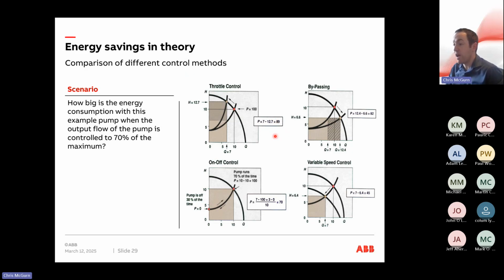So you'll see that by lowering the speed to 70% of the maximum, while using throttle control, you're down to 89% of the overall power. By bypassing, you're at 82%. On-off control, switching it on and off, 70% of the time, you're down to 70% load. But with variable speed control, you're bringing it right down to 45%. So there are significant savings to be had by removing these mechanical controls and replacing them with an electrical control.